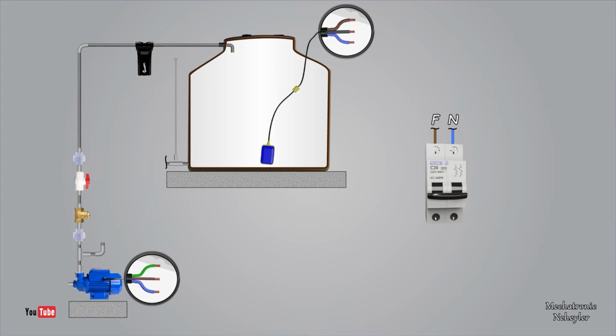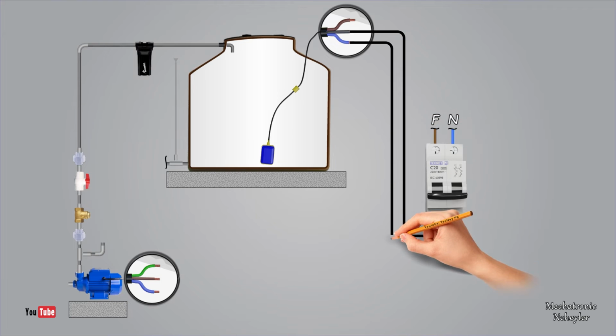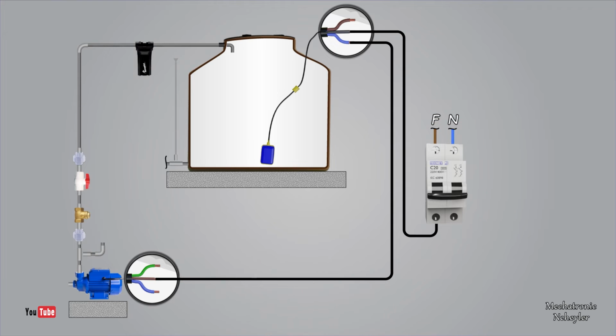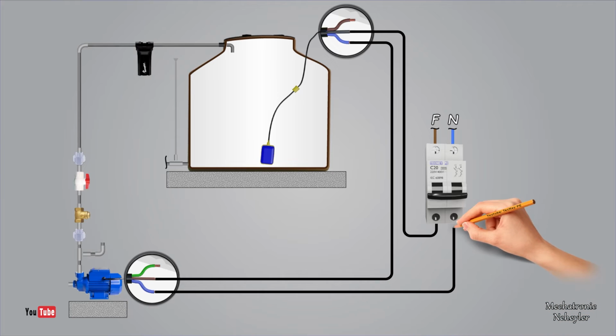The wiring should be done as follows. A cable is taken from the key or manual switch and connected to the black cable that comes with the float. From the blue or light blue cable, a cable is run to one of the power cables of the electric pump. From the other cable it is connected and brought back to the key or manual switch. It is also possible to consider a ground cable for protection on the electric pump. Remember that you must insulate the splices in the connections you made with tape or some other type of insulation, including the cables that were not used in the connection.